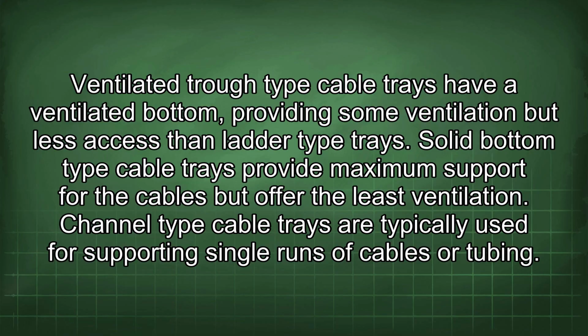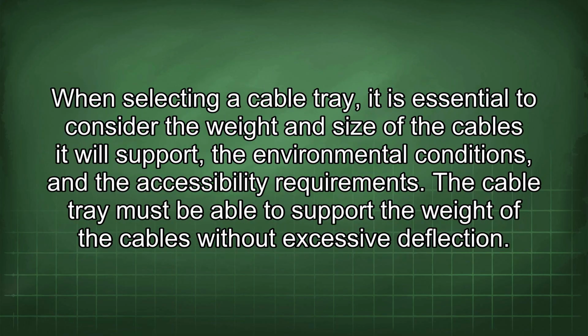Solid bottom type cable trays provide maximum support for the cables but offer the least ventilation. Channel type cable trays are typically used for supporting single runs of cables or tubing. When selecting a cable tray, it is essential to consider the weight and size of the cables it will support, the environmental conditions, and the accessibility requirements.